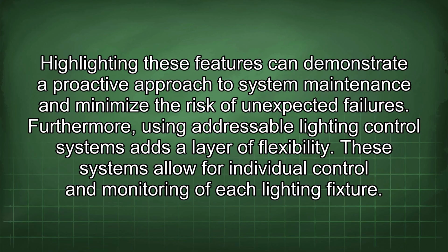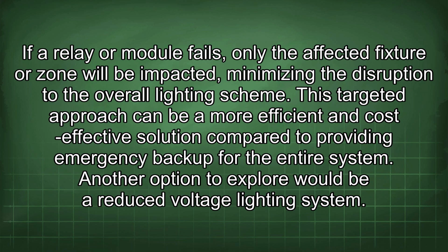Furthermore, using addressable lighting control systems adds a layer of flexibility. These systems allow for individual control and monitoring of each lighting fixture. If a relay or module fails, only the affected fixture or zone will be impacted, minimizing the disruption to the overall lighting scheme. This targeted approach can be a more efficient and cost-effective solution compared to providing emergency backup for the entire system. Another option to explore would be a reduced voltage lighting system.